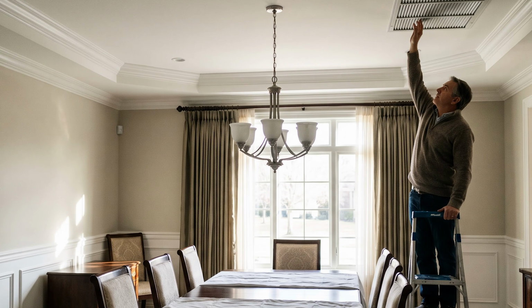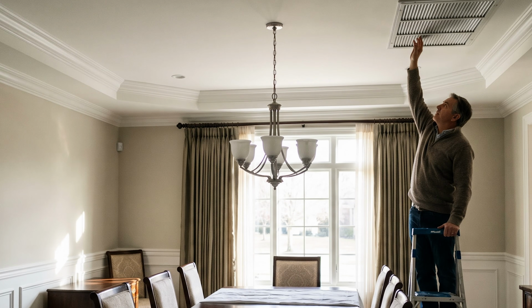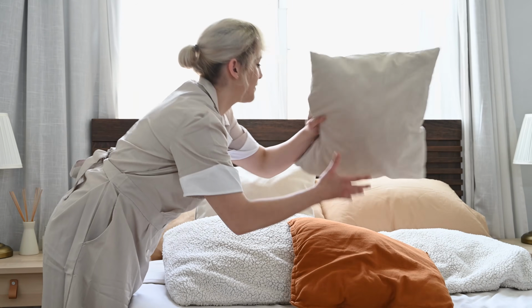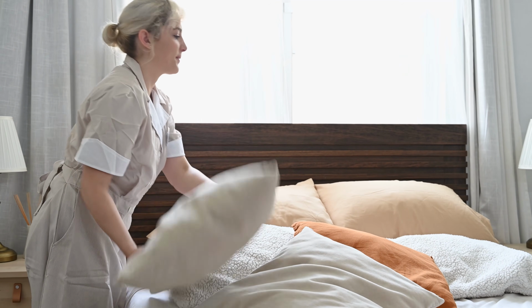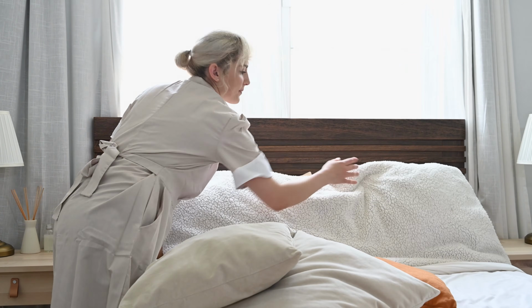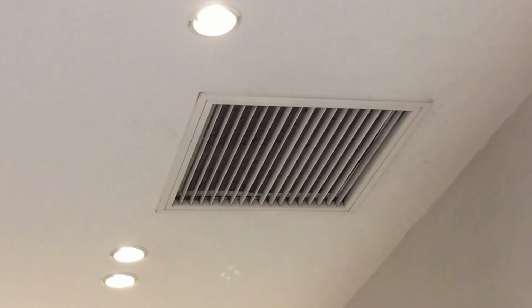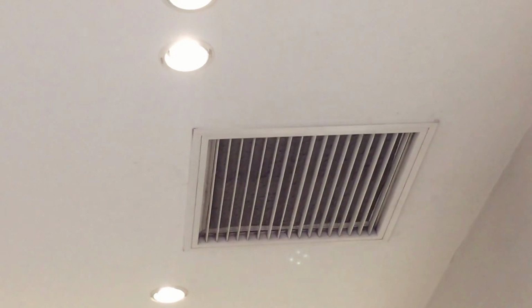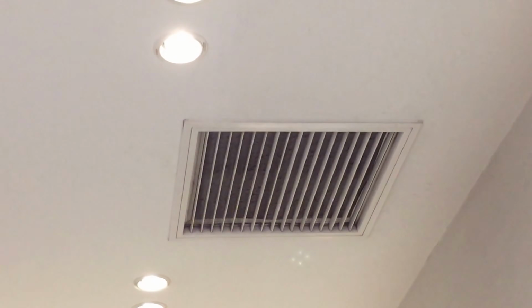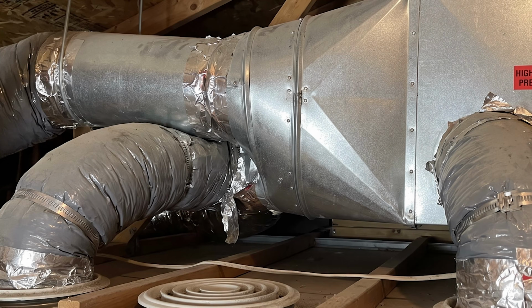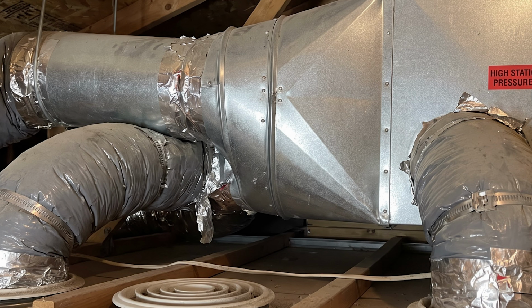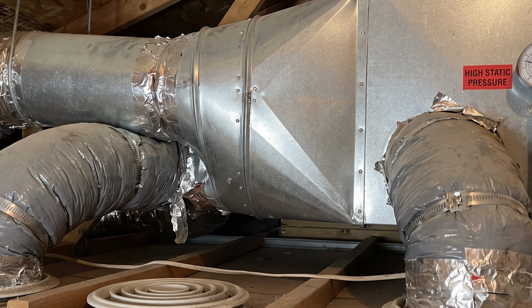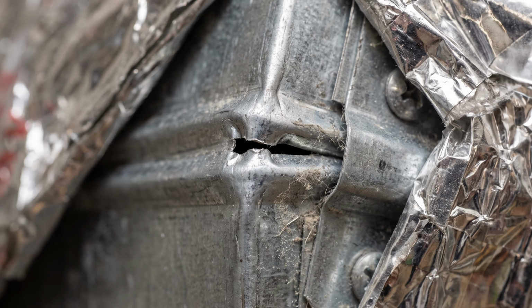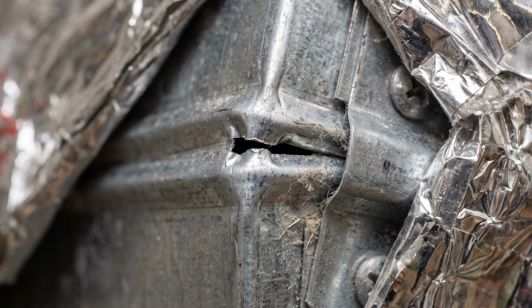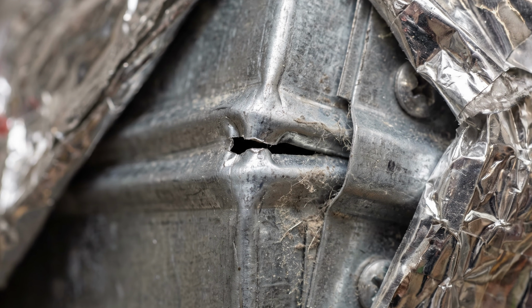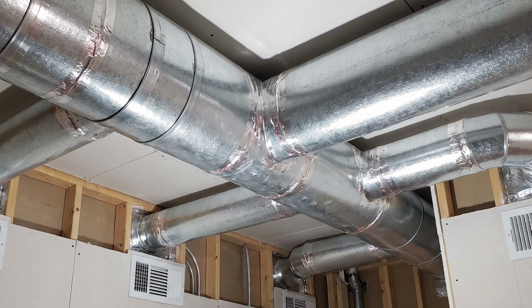HVAC repair companies love this logic because it destroys ductwork and breaks equipment. Your home cooling system was engineered to move a specific amount of air into the house and pull a specific amount of air back out. It relies on a delicate balance of pressure. When you shut the vents in a few rooms, the system does not produce less air, it still pushes the exact same volume of air into the ductwork. But now that air has fewer places to escape. This creates a massive buildup of static pressure inside the ducts. Imagine blowing air through a plastic straw and then pinching the end of the straw half closed.